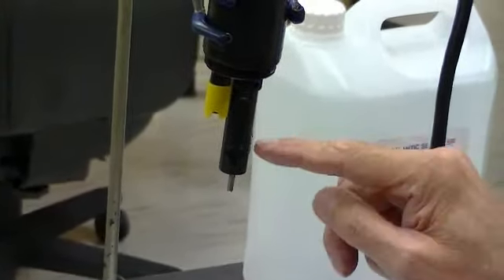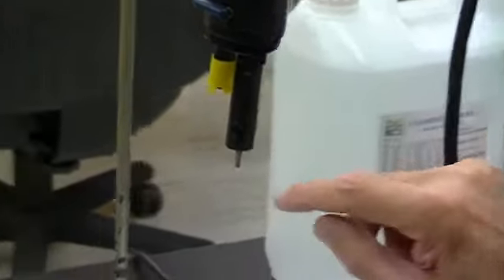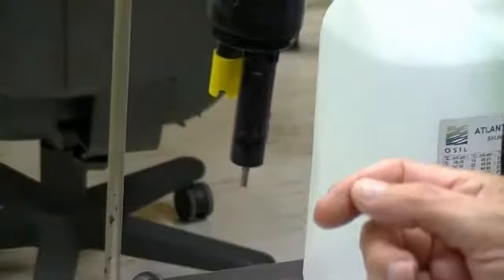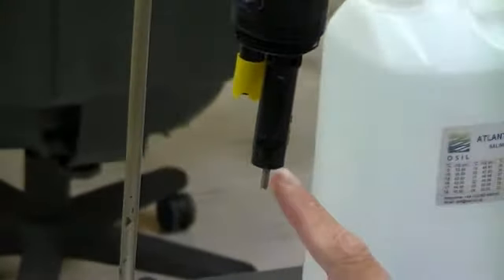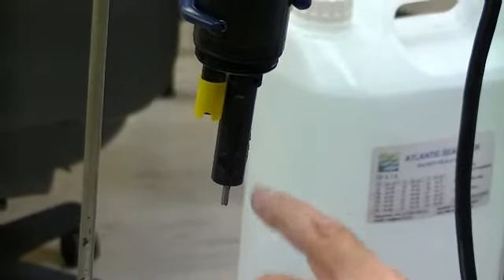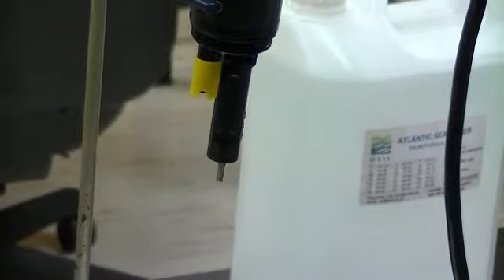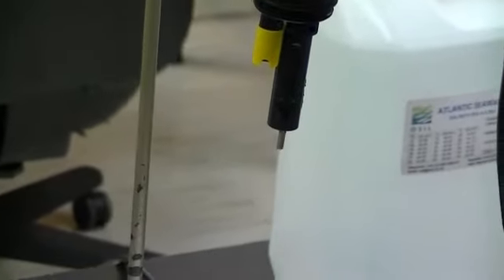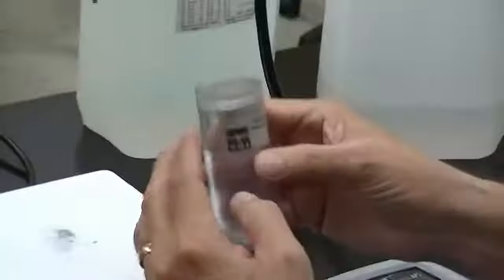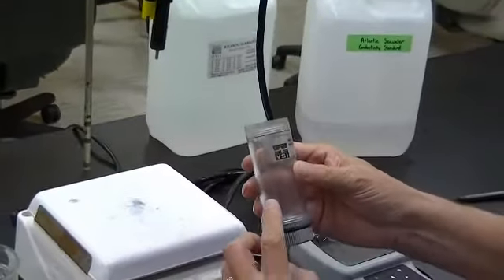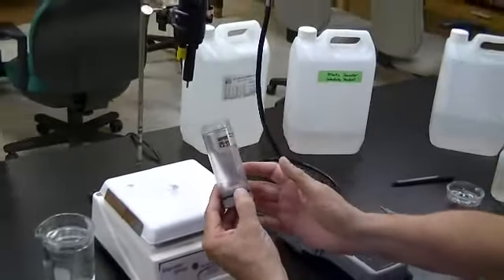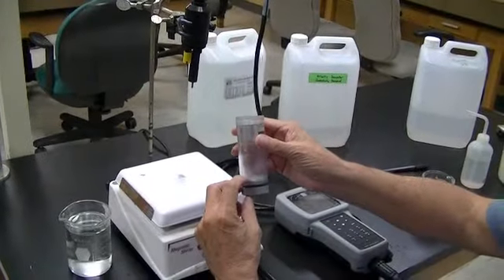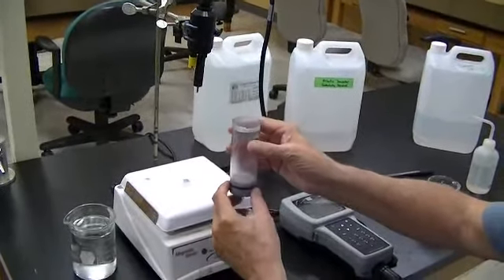Okay? The black probe has a hole in the side of it, and I don't know if you can see it from in the video, but you certainly can when you look at it. It has a big hole in the side of it, and then it has a hole in the bottom. And inside that, in the channel there, are where the electrodes are that sense the conductivity. Okay? So the first thing you do is you come in and you will find the probes in air. The conductivity chamber should be empty, except for just a little bit of water to keep the oxygen probe hydrated.